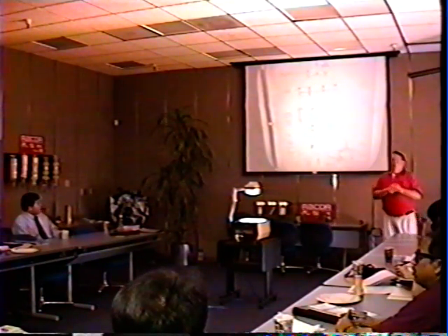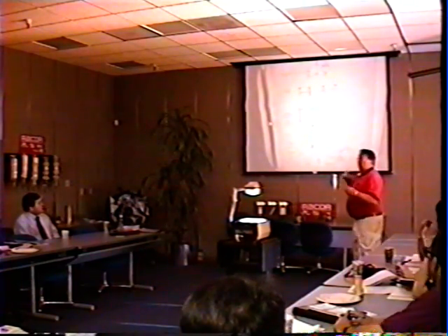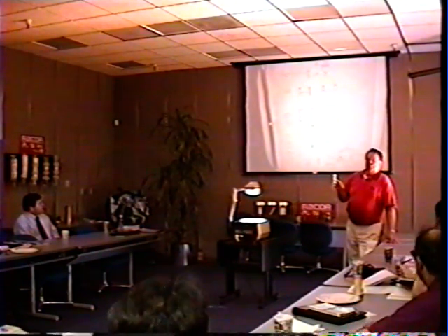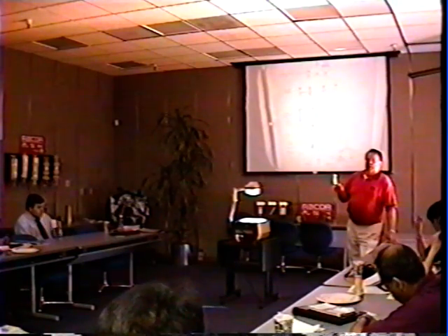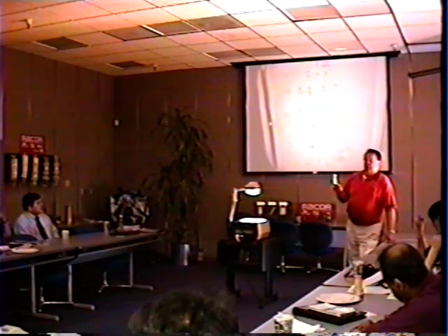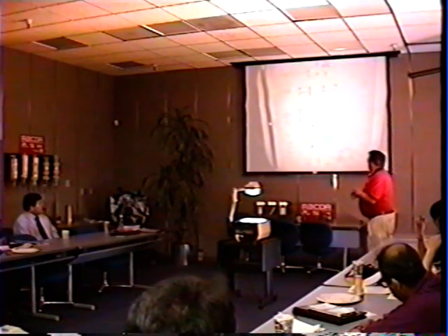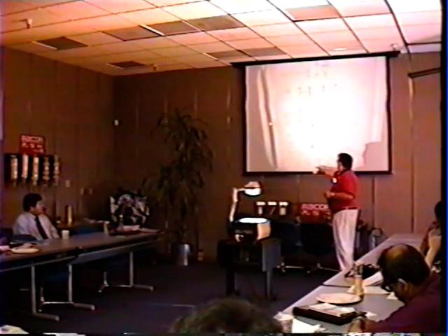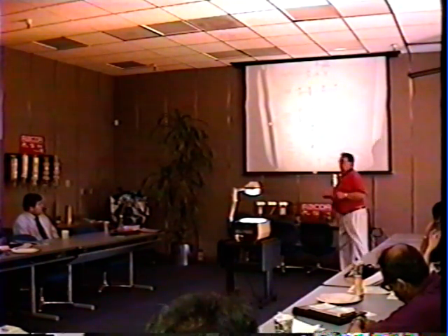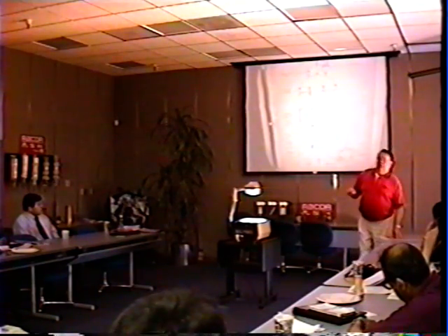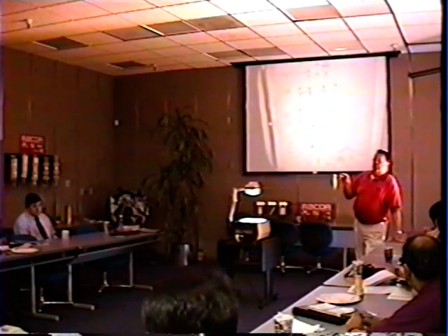Now, part of the API, the final part of it, is we're flowing in the vessel you'll see this morning 500 gallons a minute, and the final test is 3% water. So how many gallons of water is that we are removing from the fuel per minute? 15 gallons a minute. So when you look inside of the vessel, it looks like it's raining. And the sump with our drain, in our case we used a manual drain, was like turning the hose on full blast. Because out of your 500 gallons per minute fuel flow, you are injecting 3% water, 15 gallons per minute.